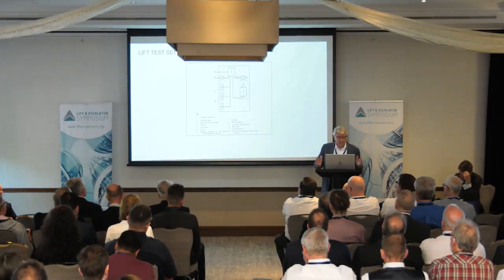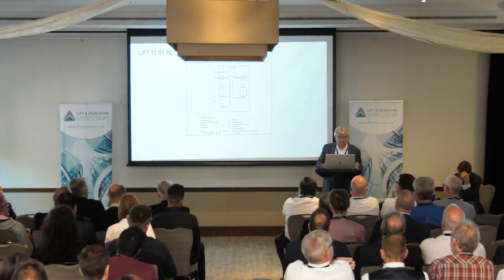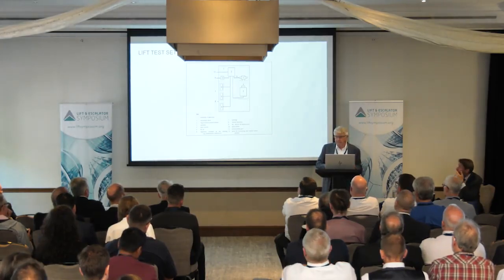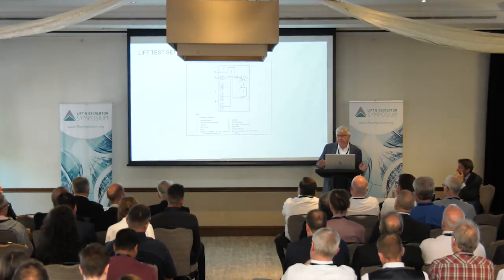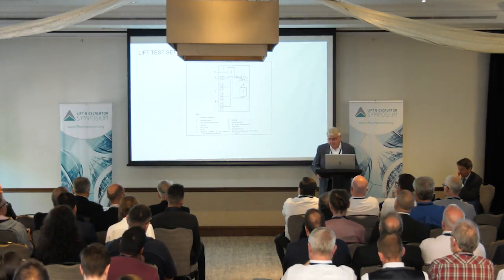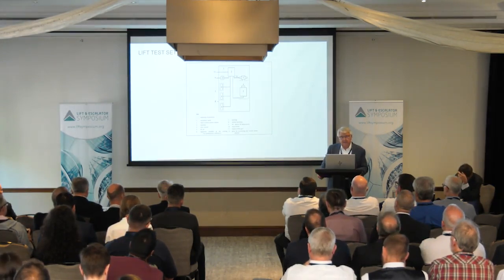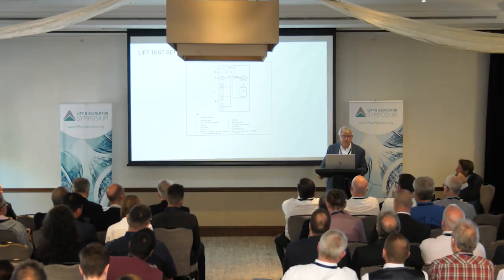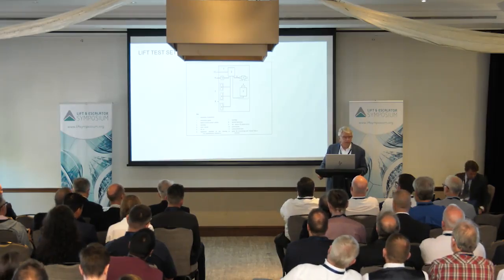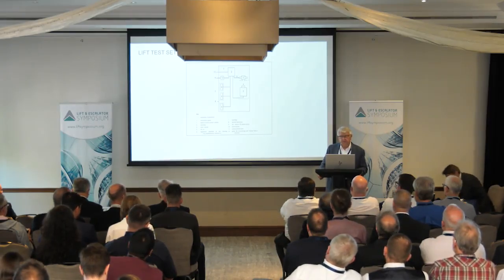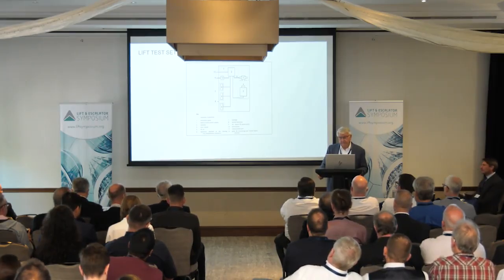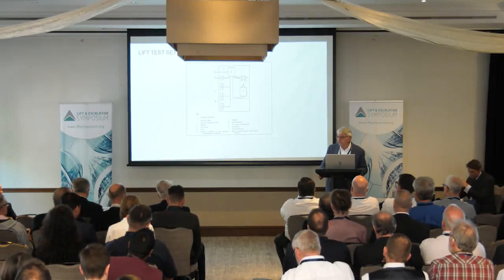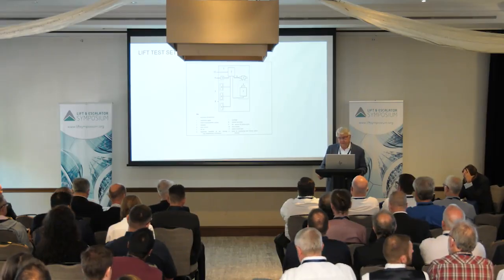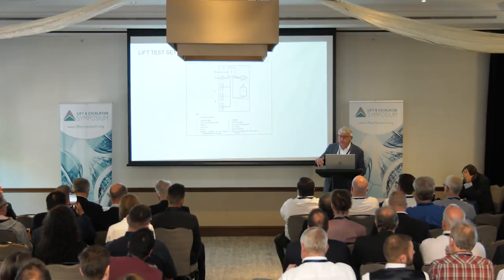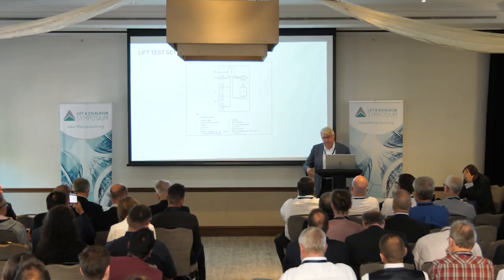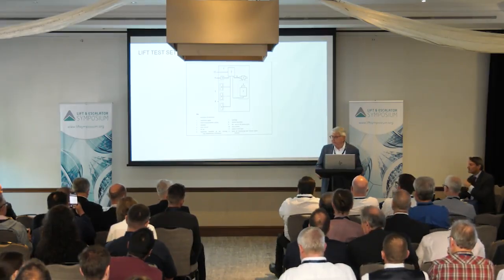The standard says you have to have a set of instructions telling you how to install this. I know they exist, but I've never seen them in the field. Most everything in the Middle East at that time was installed by unsupervised contractors. When you're using subcontractors, you better have more supervision than with your own forces, or you get nothing. Because you don't get what you expect, you get what you inspect. And if you don't inspect, you don't get anything.